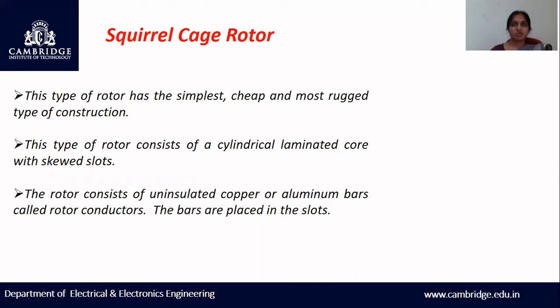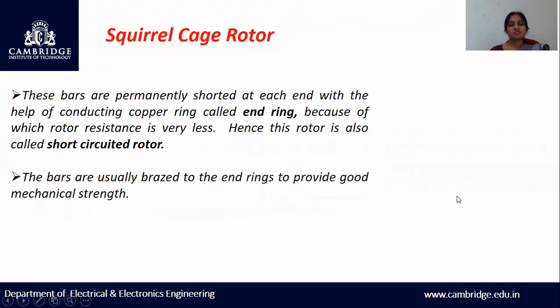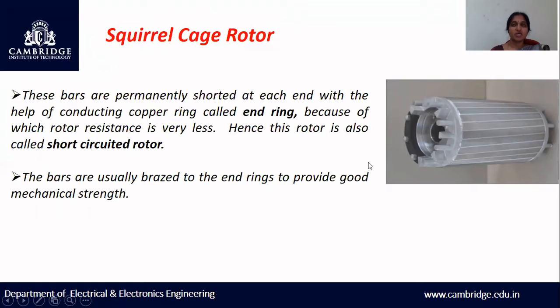The squirrel cage rotor has the simplest, cheapest, and most rugged construction. It consists of a cylindrical laminated core with skewed slots, where conductors are placed. The rotor consists of uninsulated copper or aluminum bars called rotor conductors, placed in the slots. These bars are permanently short-circuited at each end with copper end rings, making the rotor resistance very low. This structure looks like the cage of a squirrel, which is why it is called a squirrel cage rotor. The bars are usually brazed to the end rings to provide good mechanical strength.